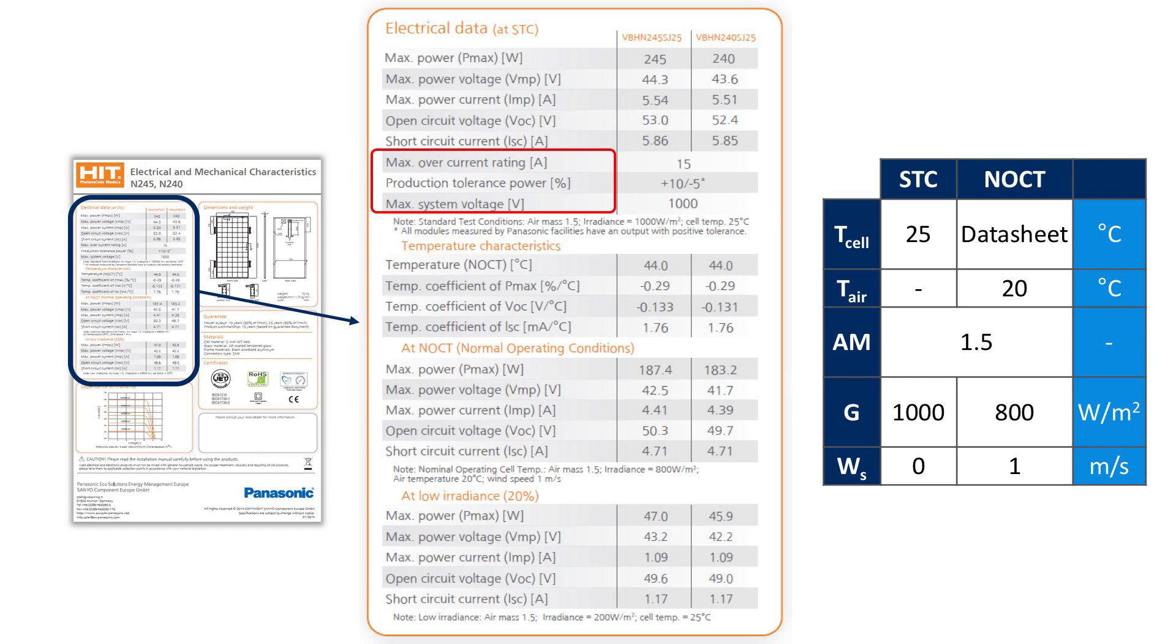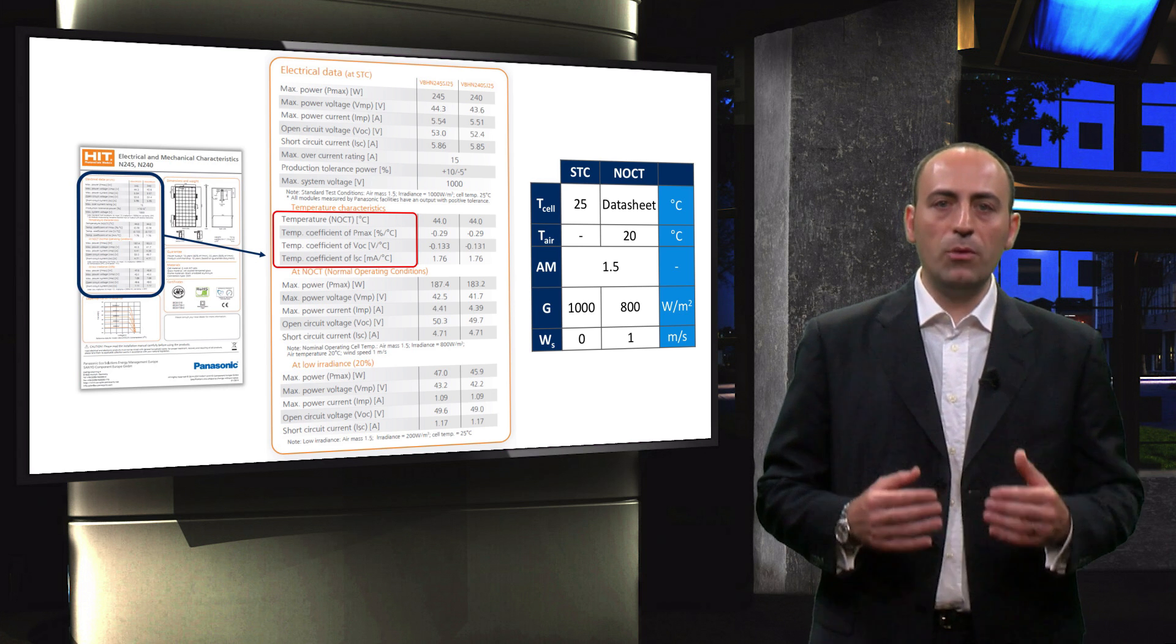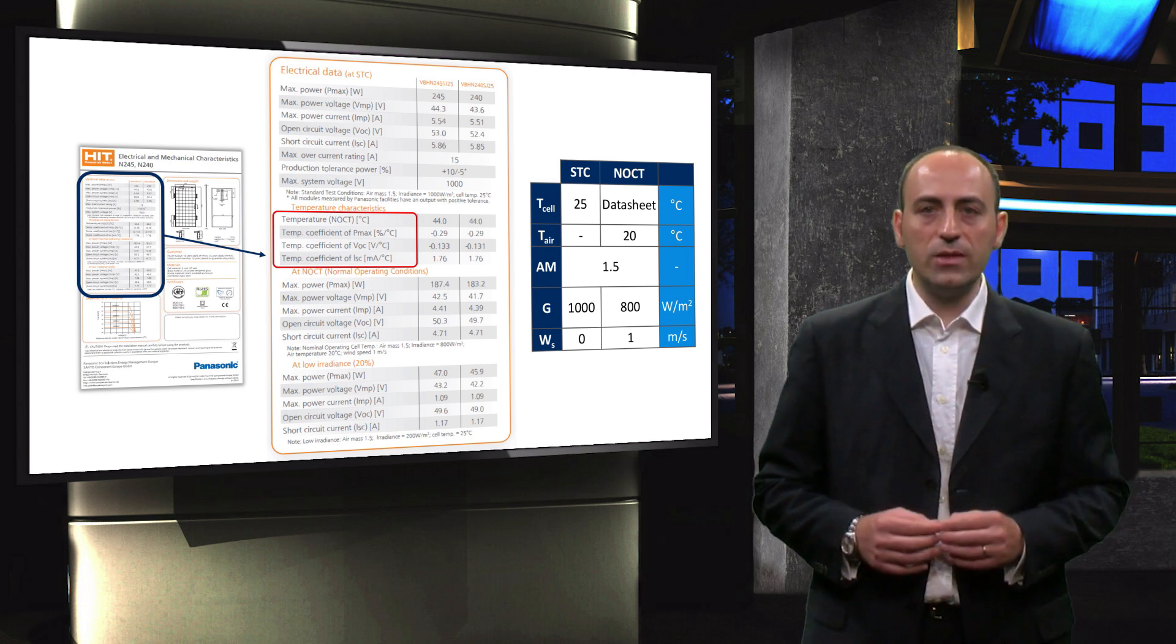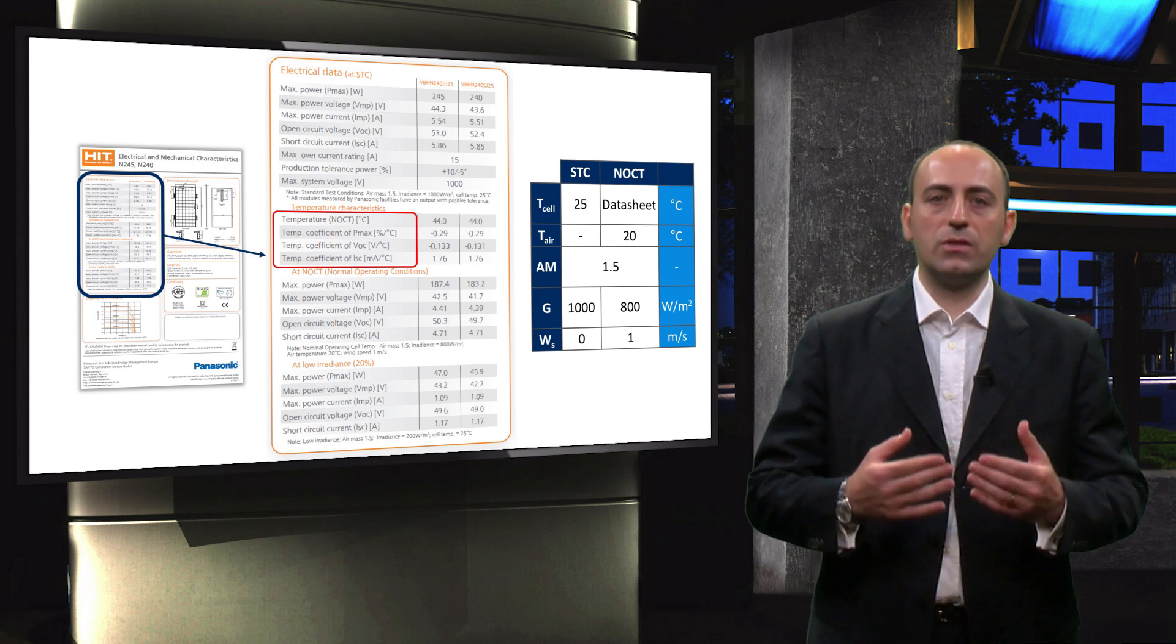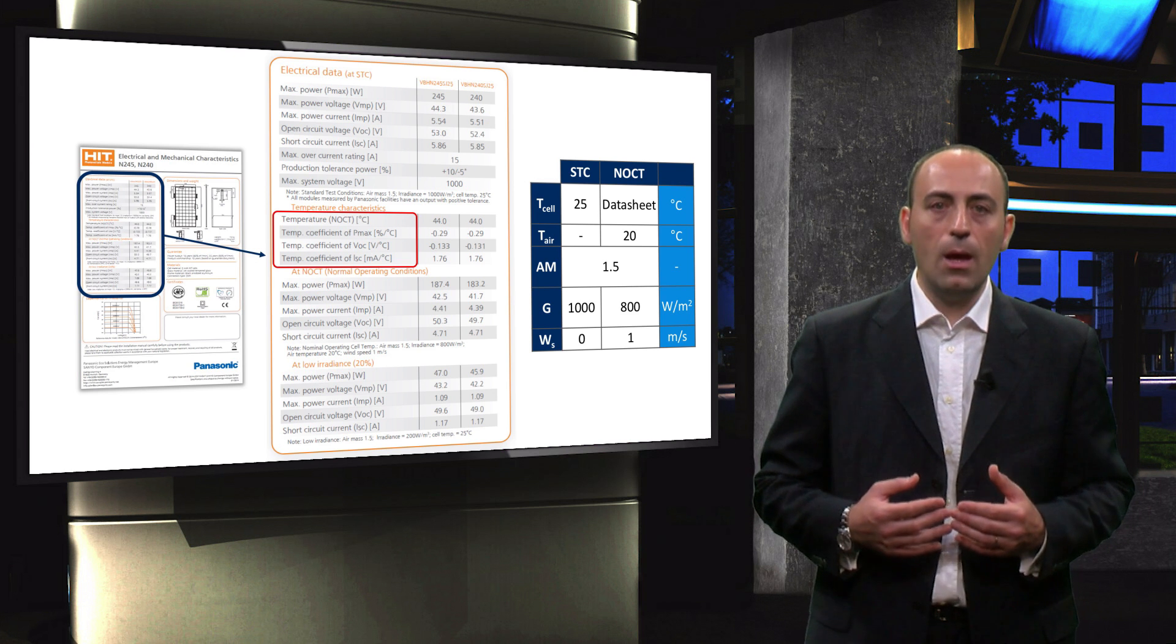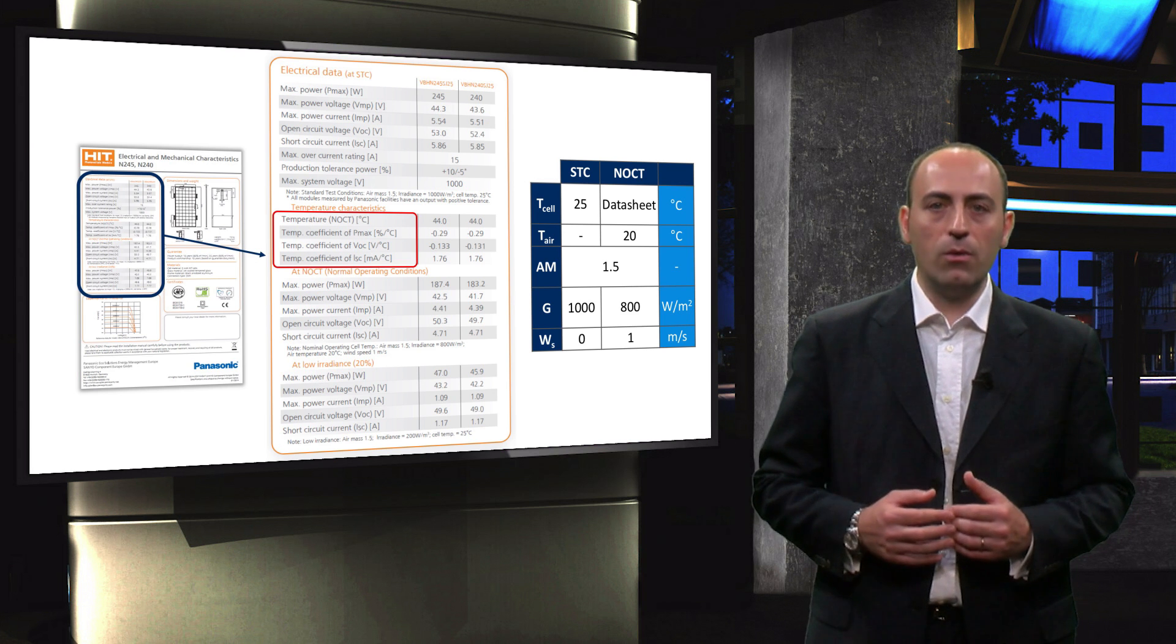I already anticipated that the second table gives the temperature coefficients of maximum power, open-circuit voltage and short-circuit current. They are very important, since the temperature of the solar cell has direct influence on the power output of the PV module. In fact, as you can see, high temperatures increase the short-circuit current, but decrease both the voltage and the maximum power achievable.